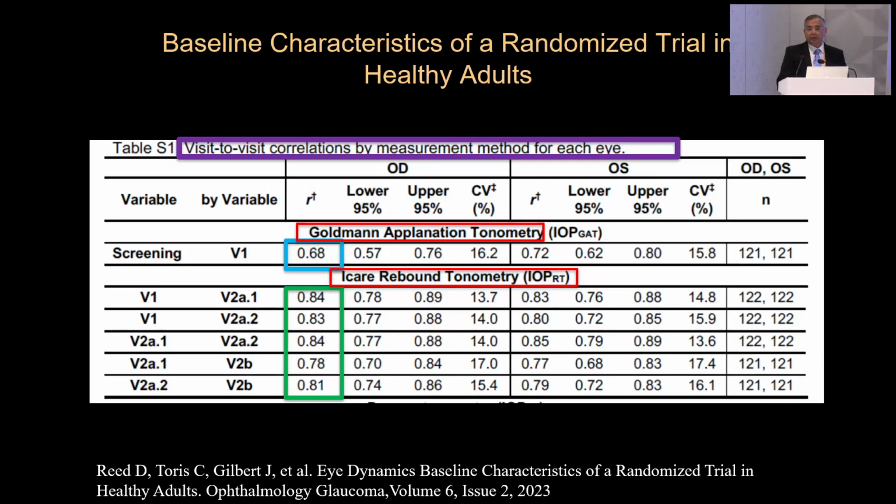This tonometer is the only tonometer that we can use which doesn't require an anesthetic apart from the air puff tonometer. This tonometer, thankfully, is agnostic to which individual is using it, because it gives you an average of 6 readings. Secondly, the patient is not straining into the slit lamp when somebody is measuring this thing.